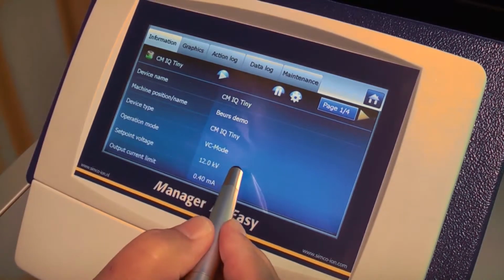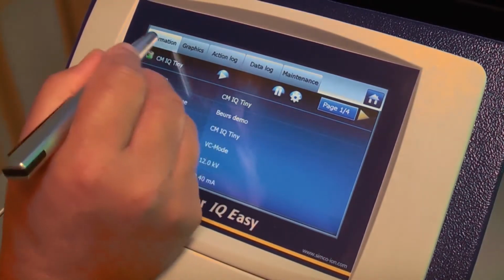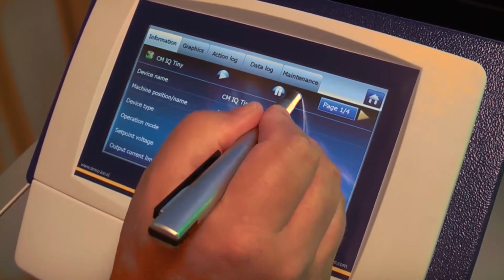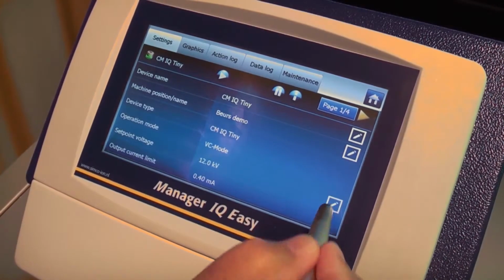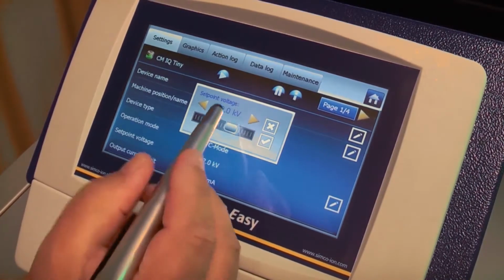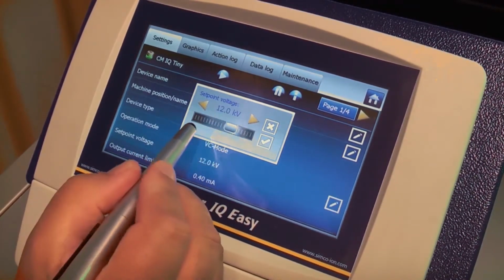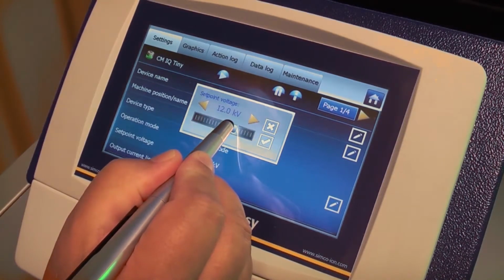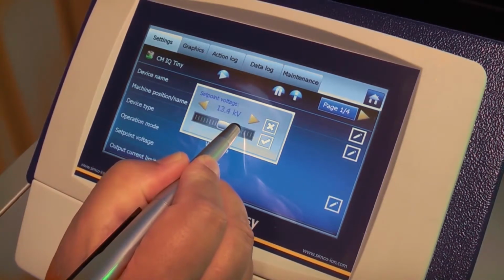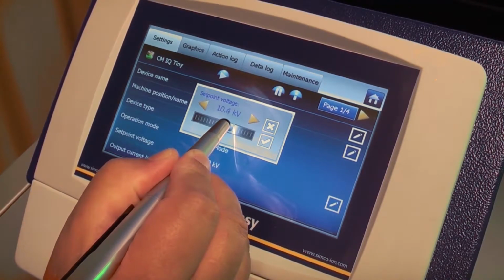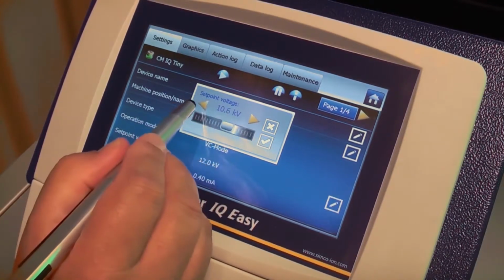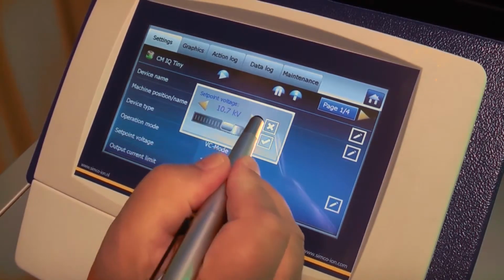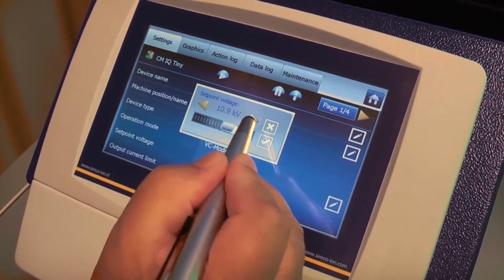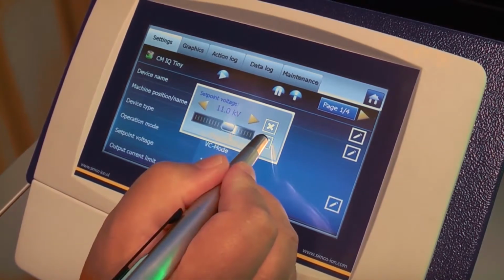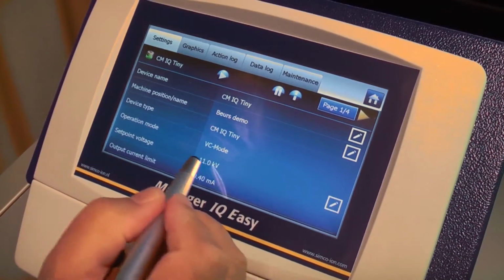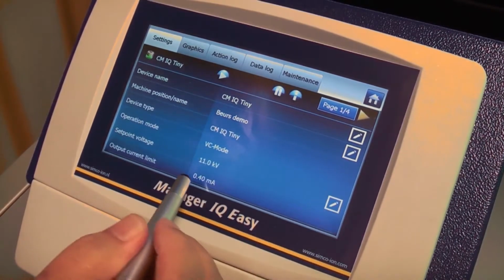If I want to change this, for instance, to 11 kilovolts, I'll have to go, now I'm in information mode, I have to go to the settings mode again, change the set point. In this case it is 12 kilovolts. When I want it to 11 kilovolts, I can use this slider here to go up and down. Now I'm at 10.6 kilovolts. When I want exactly 11 kilovolts, I can use the little yellow arrows to get it on exactly 11 kilovolts, acknowledge, and now I have set my set point to 11 kilovolts.